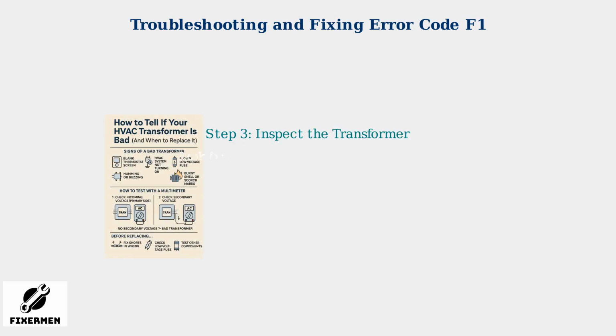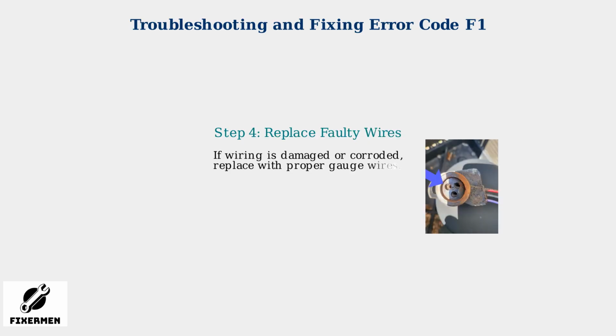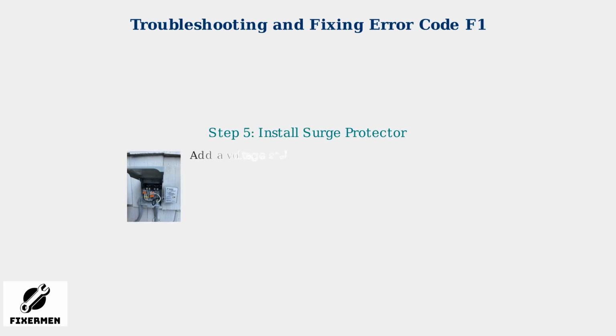Inspect the transformer for signs of damage or failure, such as burning, scorch marks, or blown low-voltage fuses. A faulty transformer is a frequent cause of F1 errors. If wiring issues are found, replace any faulty or corroded wires. Ensure connections are secure and use the correct wire gauge for safety. Consider installing a surge protector or voltage stabilizer to protect against power fluctuations that can trigger the F1 error.